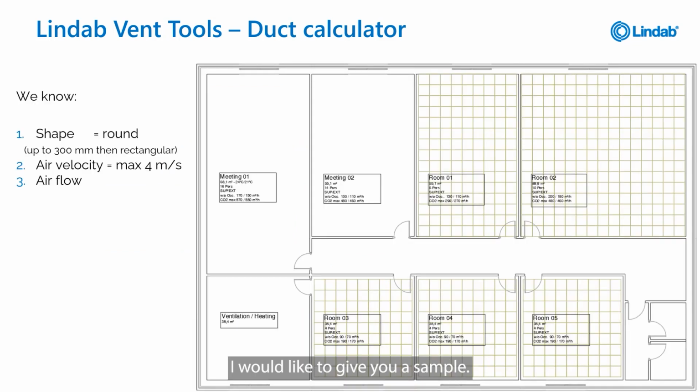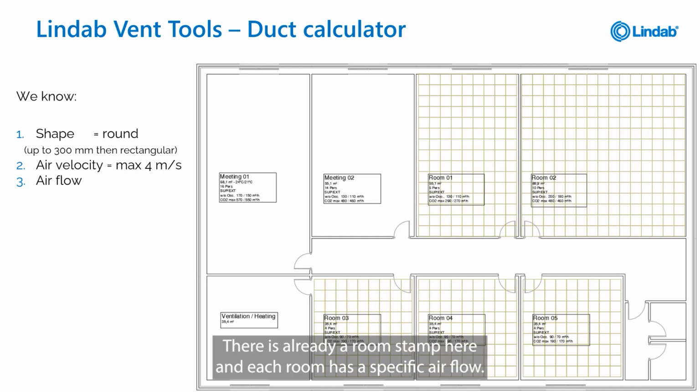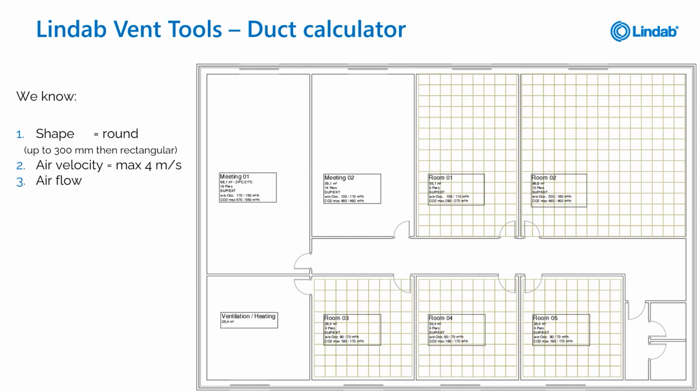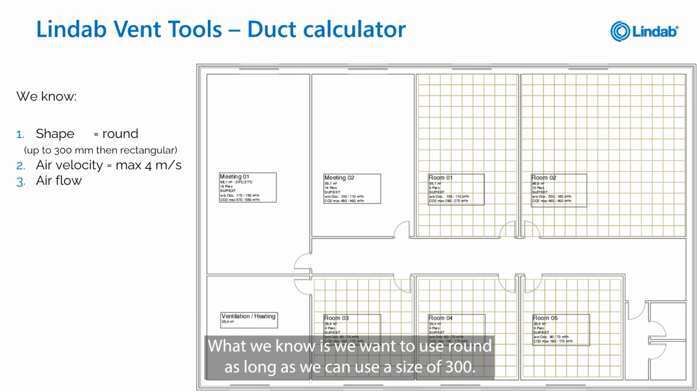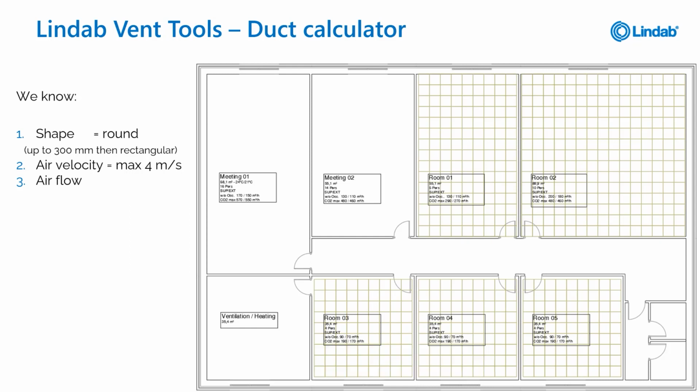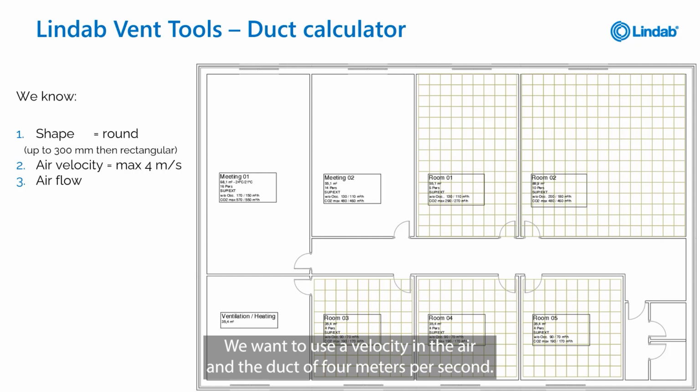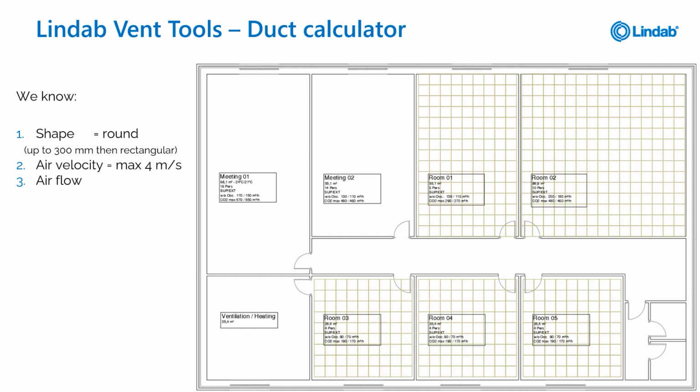I'd like to give you a sample. This is a small building. There is already a room stamp here, and each room has a specific airflow. What we know is we want to use round ducts, with a maximum size of 300, and we want to use an air velocity in the ducts of 4 meters per second, and we know again the airflows from the rooms.